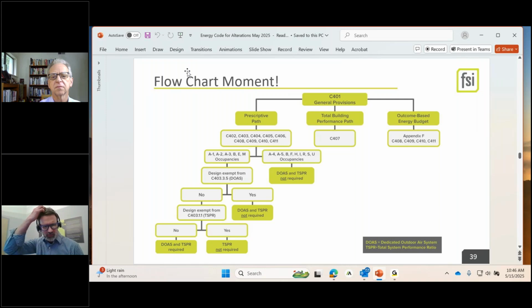Duane said 1 in 5 buildings fails. I don't know if that's all or just existing buildings that they're reporting back on. I would expect higher than that. We have many projects where we've said, great, we're replacing the mechanical equipment. Oh no, our TSPR doesn't pass, and it's by enough of a margin that we need to go do something else in that building to save energy. Lighting, sometimes windows, air seal. There's a wide list of how you get down below your TSPR target.